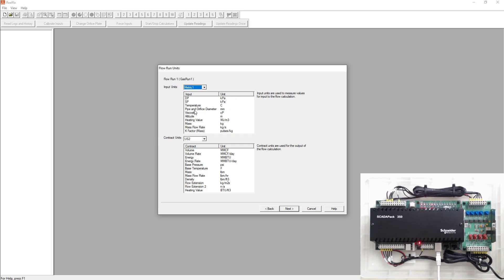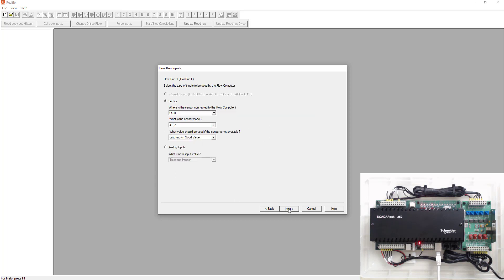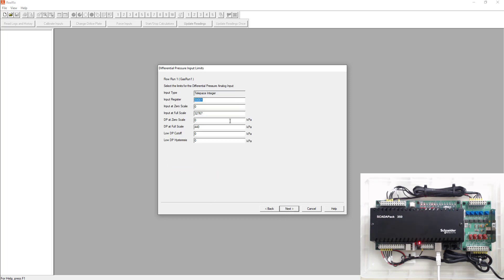Next I'm going to ask you what your input units are. We're going to use metric one for both input units and contract units. So they're both the same. Typically I use metric one for gas and metric four for liquids. Next it's typically you connect to a 4102 multivariable over Modbus. But in this simulation application, we're just going to use the analog inputs of the SCADA pack. So we're going to use analog 0, 1, and 2 for static differential and temperature. So the three components will be coming back from your multivariable. We're just going to simulate with the three analog inputs. So we'll pick analog input. We're using Telepace. So we'll go Telepace integer. Hit next.